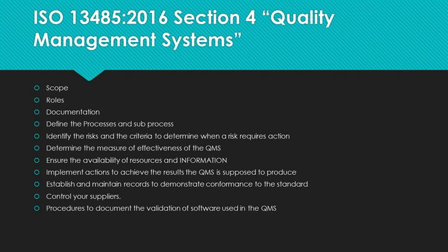You need to define roles. They must be documented and identify the applicable regulatory responsibilities and authorities to each role. If the FDA must be notified, who is doing what tasks, who collects documents and reviews complaints for reportability? Having an employee unclear about who they are reporting to or what they are reporting is not an acceptable reason for missing reporting an incident. You are also going to have to consider documentation when you are developing the QMS.